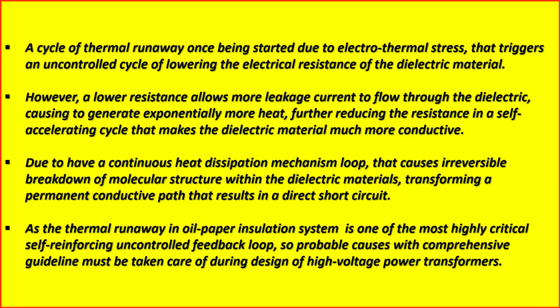As the thermal runaway in an oil paper insulation system is one of the most highly critical self-reinforcing, uncontrolled feedback loops, probable causes with comprehensive guidelines must be taken care of during the design of high voltage power transformers.